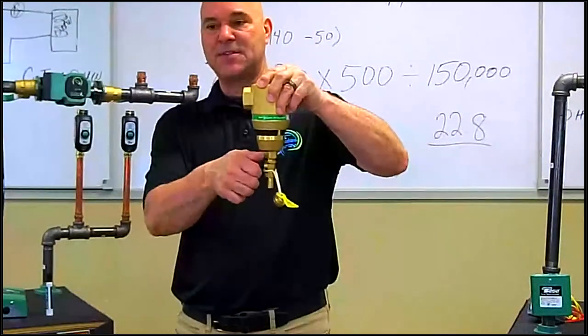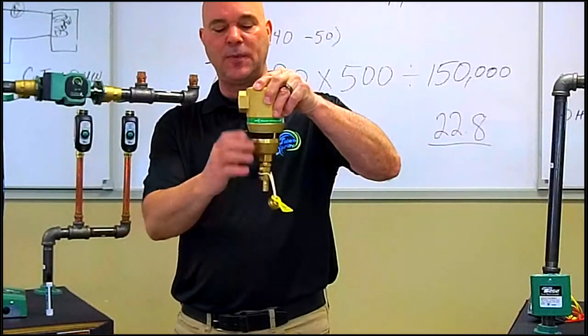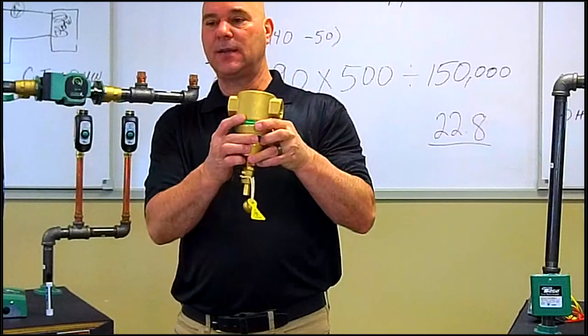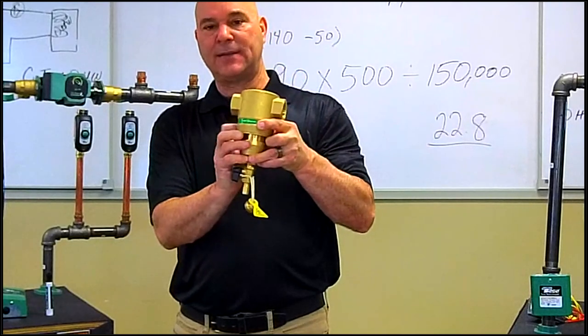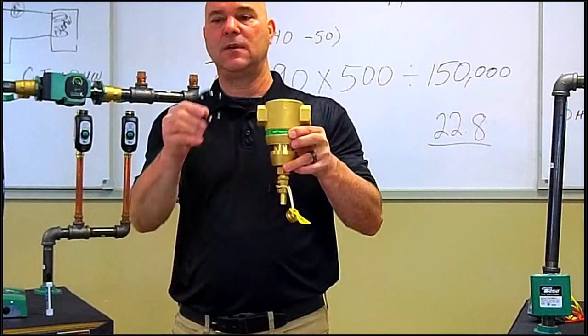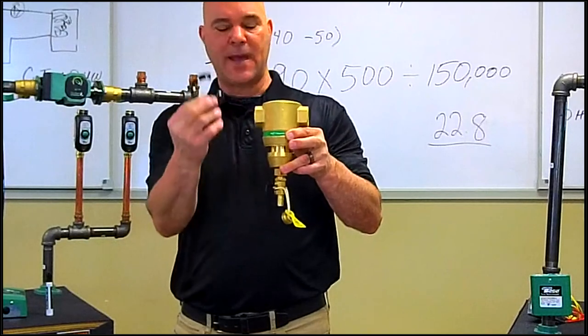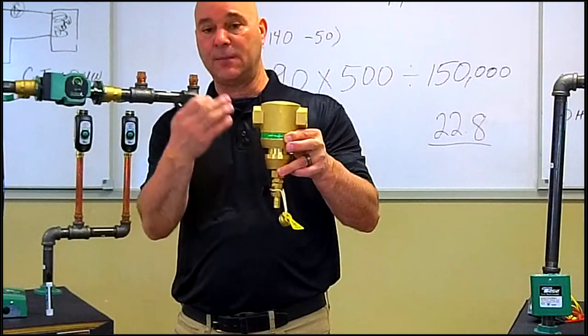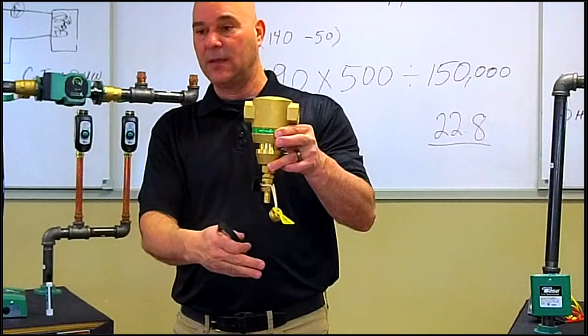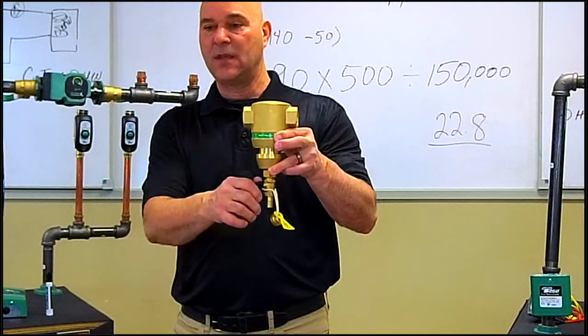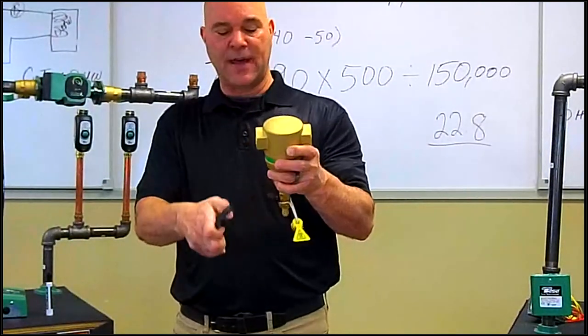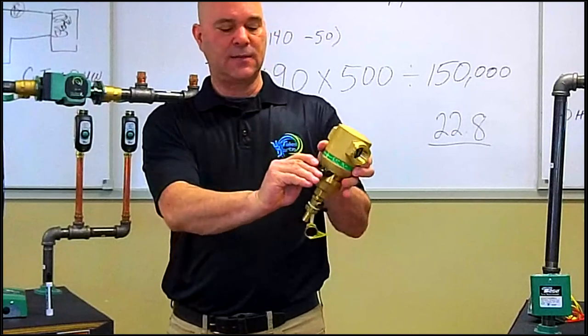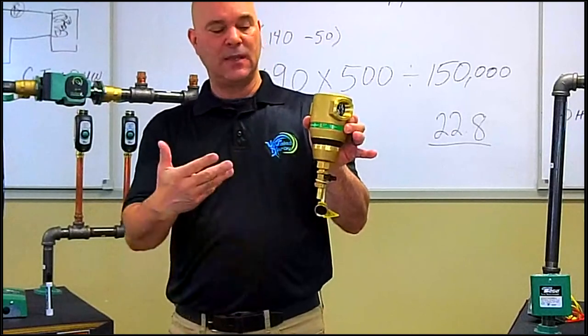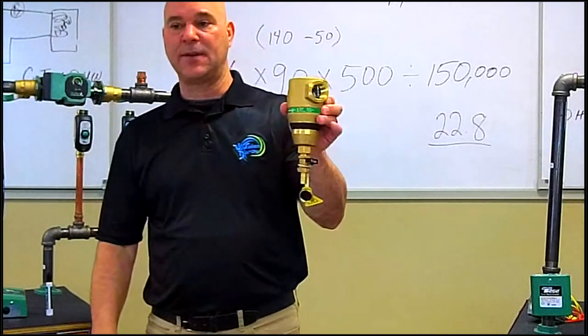So you would get to the job site. If you want to flush out the system, you would open this valve. You would take and pull this magnet strip off. And while this magnet strip is off, all the dirt and metallic pieces within the system would be flushing out of the system. After you're done, you would close the valve. Just take this magnet, pop it back on, and you're back with your mag dirt separator here.